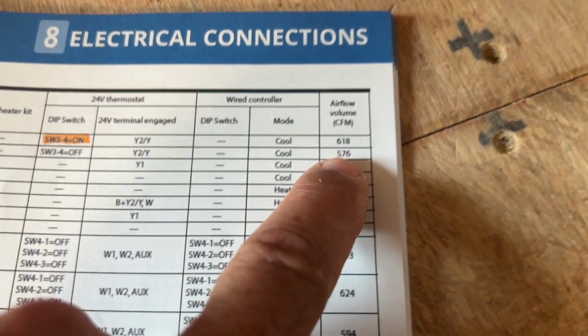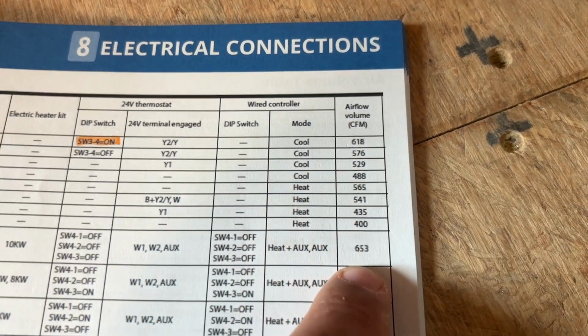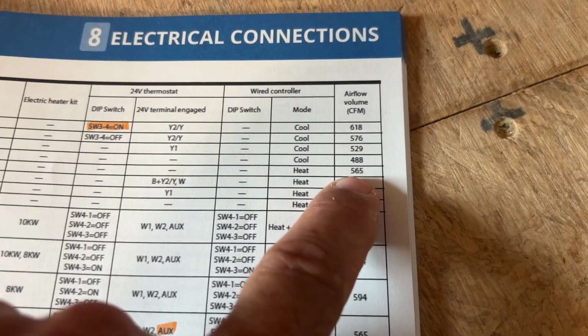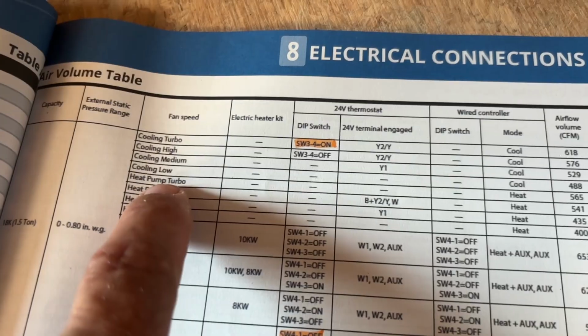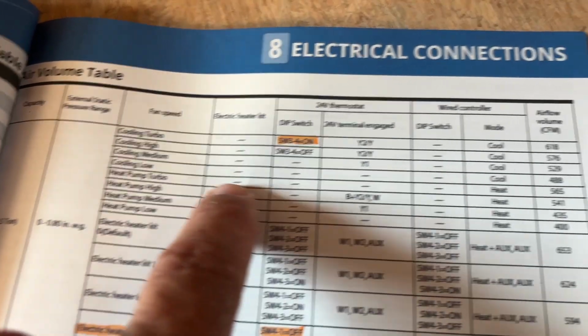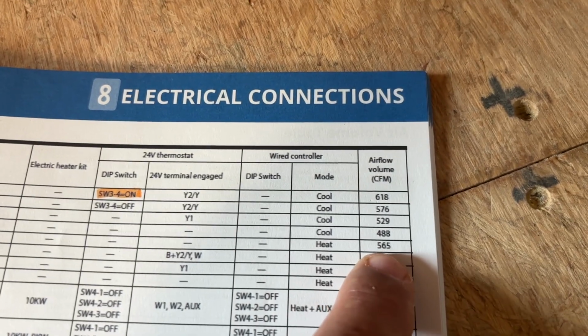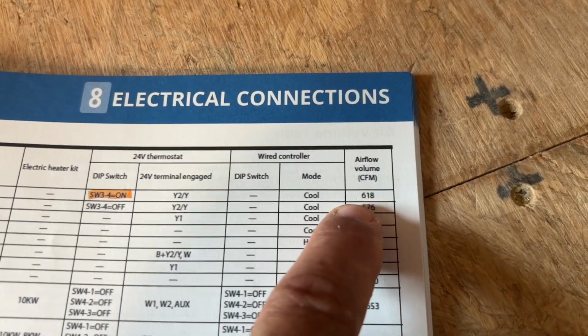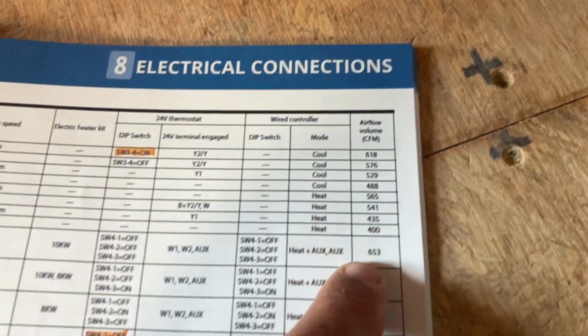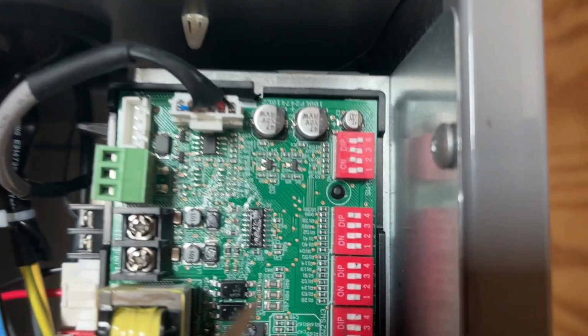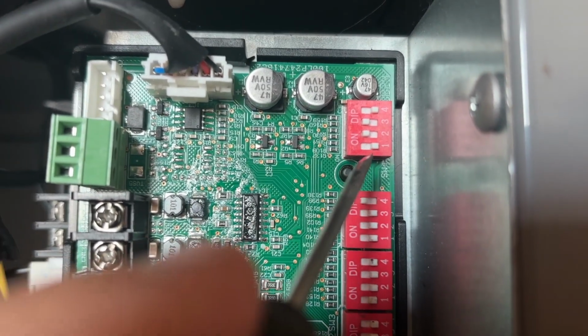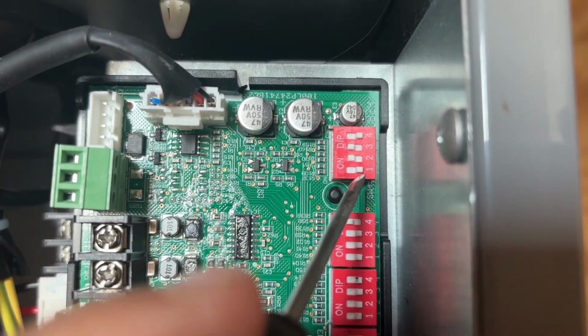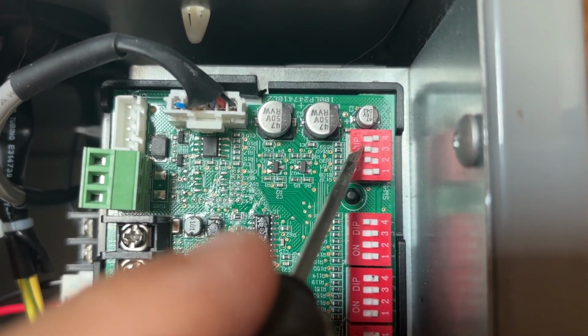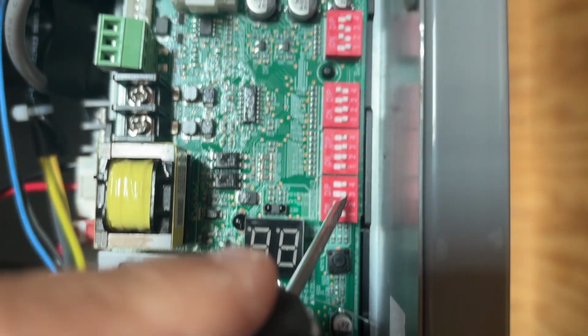So just as a comparison, it'd be similar to the high mode in cold. 565 is actually the heat, and that is heat pump turbo in the heat mode. So it puts a little more CFM out in the cold mode than it does in the heat mode. So let's go ahead and look at those switches. So SW 1, 2, 3. So I have 1 off and 2 and 3 set to on.